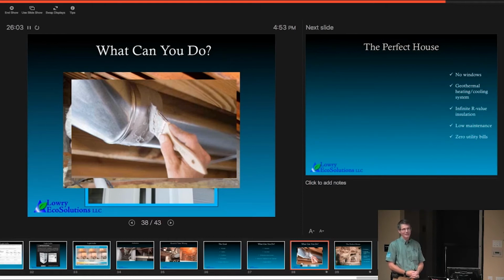See, that's the unfortunate thing I hear all the time. Unfortunately, they're just little gaps, but, well, this is what I tell my clients, it's death by 1,000 pinpricks. If you have little gaps that you can see, some places you may have big gaps, and you add up all those little gaps, and now you've got the size of a window in your duct system. I would say if it's pretty easy to do and you can get to them, you should seal every gap you can find, because there's going to be some you can't get to, and I don't ever say rip walls out to get to your duct systems.